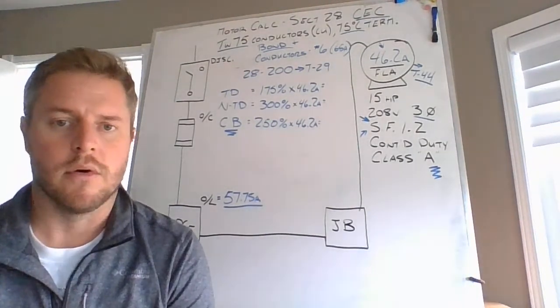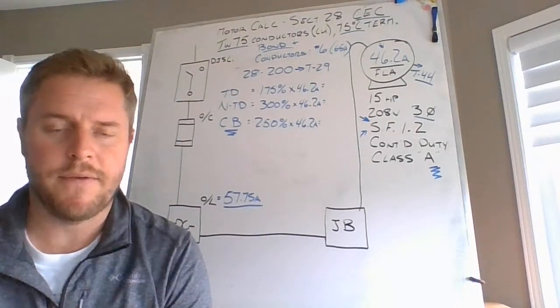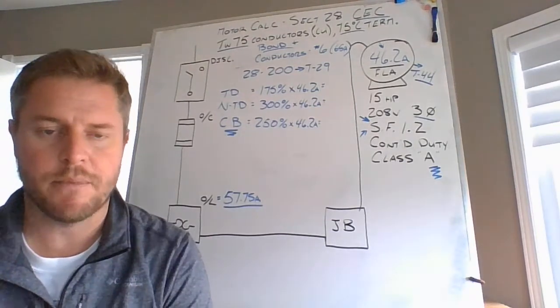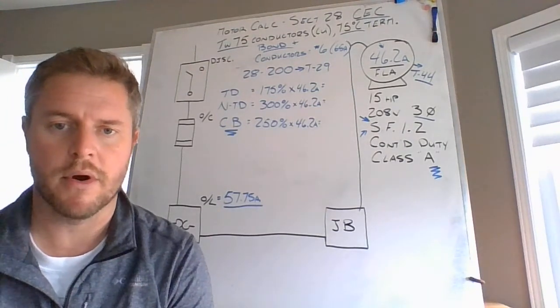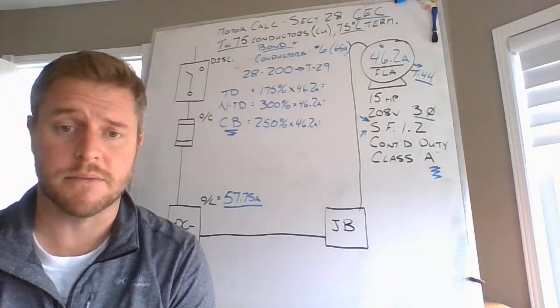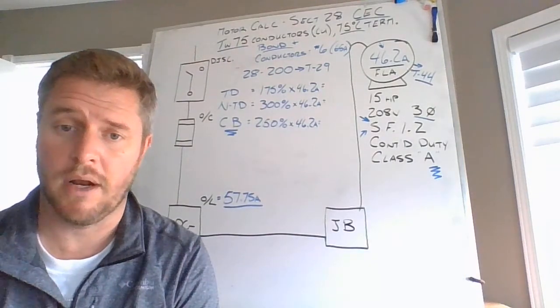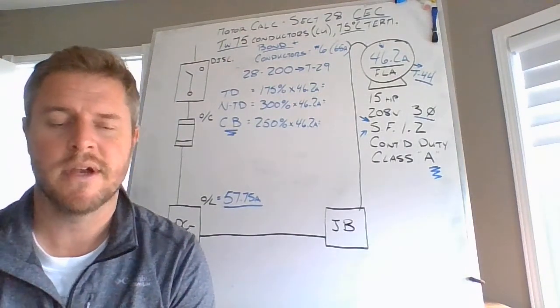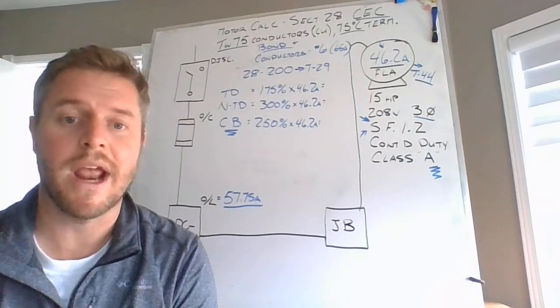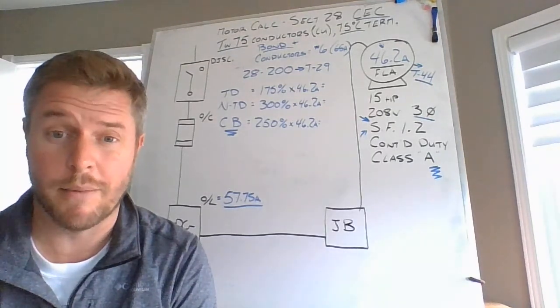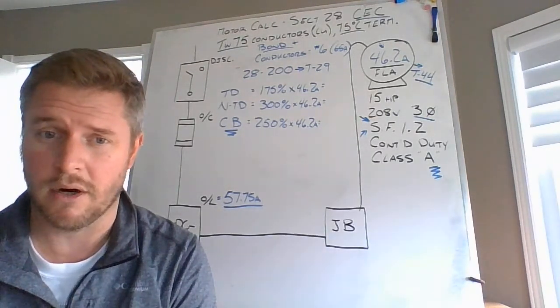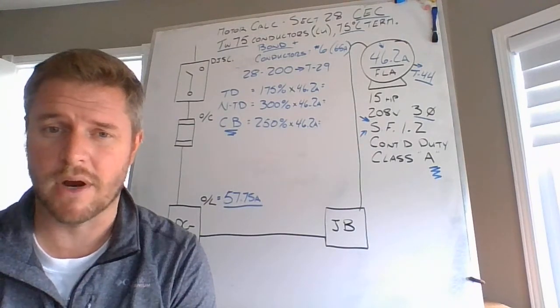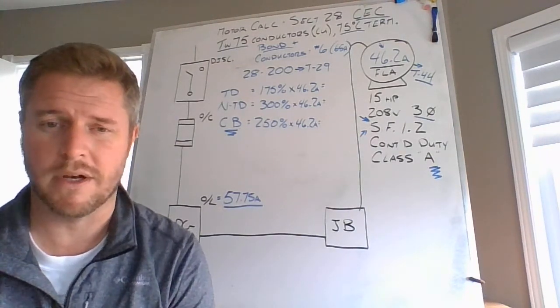Okay, so now we're looking at time delay fuses being 175% of my full load current rating of my motor. I'm looking at non-time delay fuses being 300% of the full load current rating of my motor, and circuit breakers being 250% of the full load current rating on my motor.